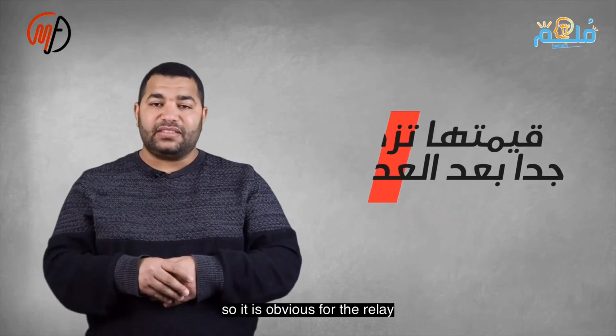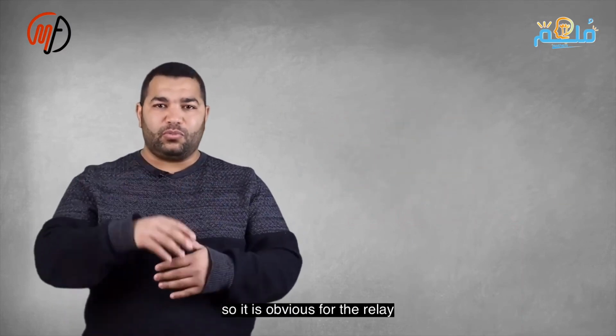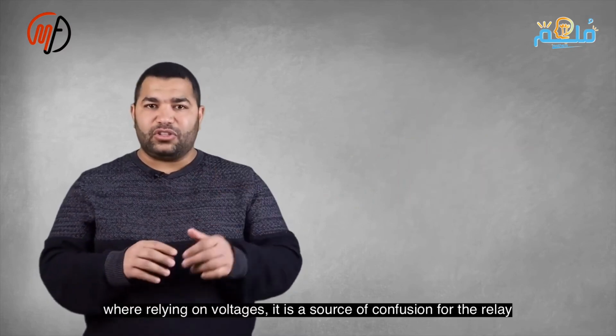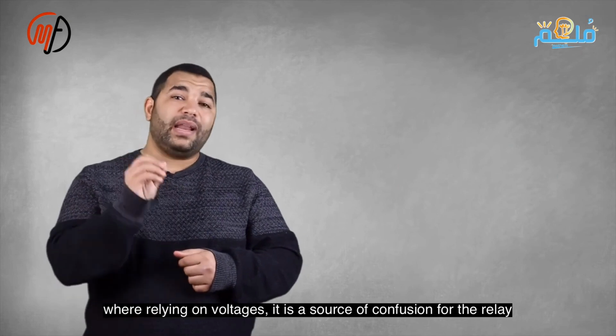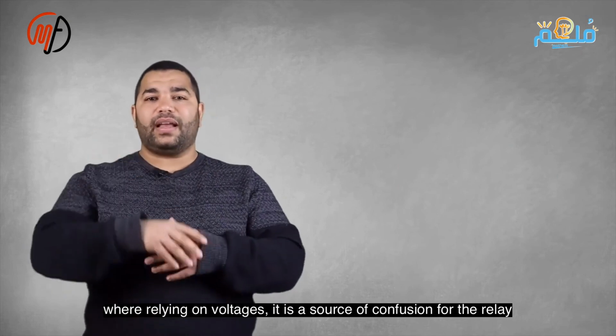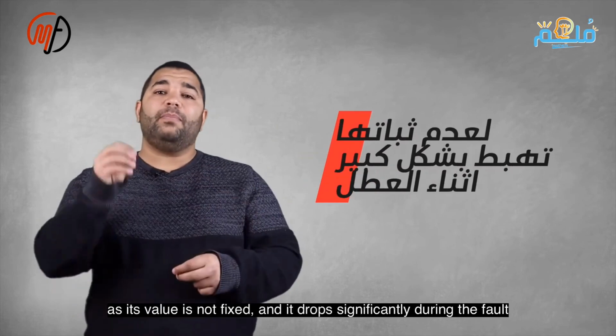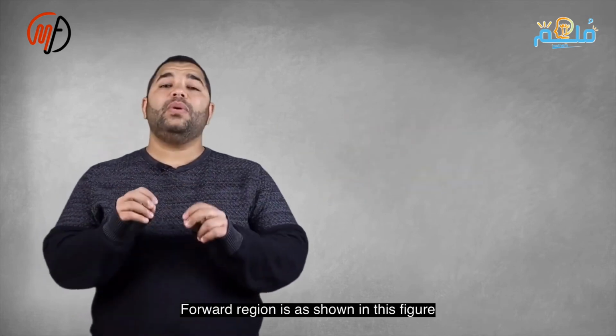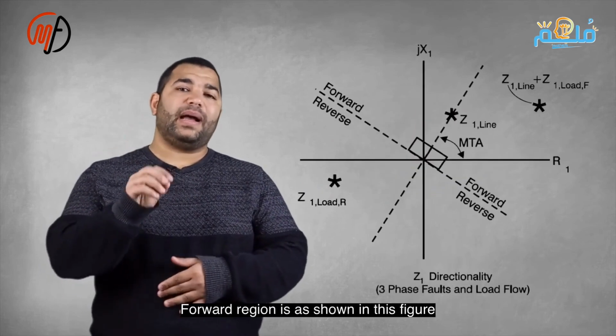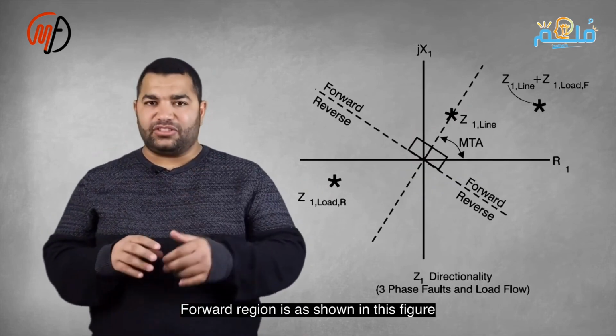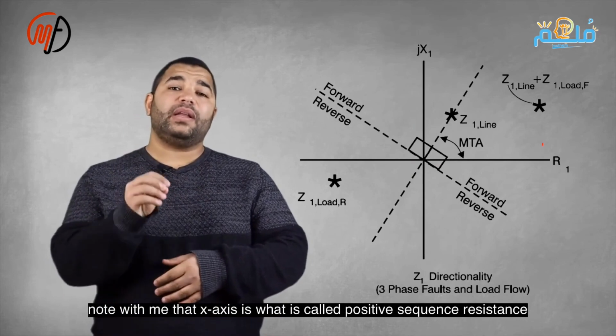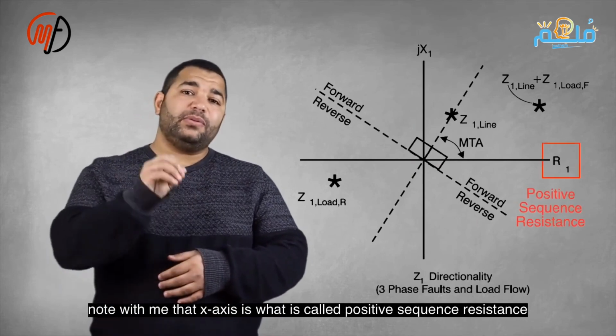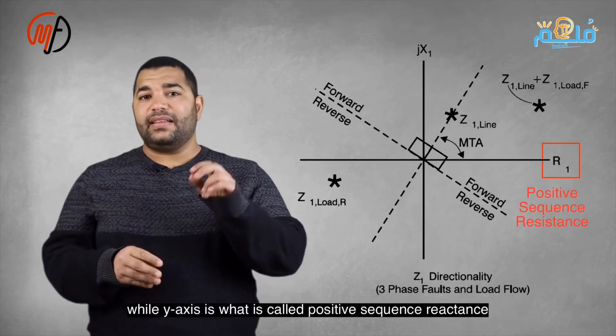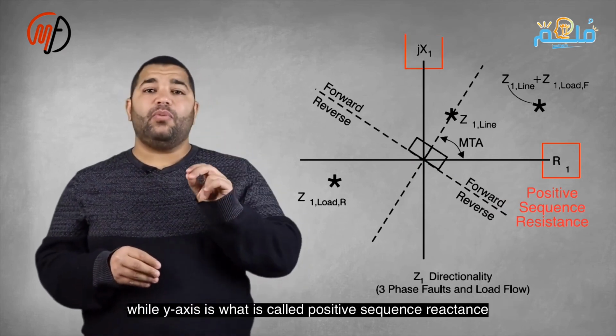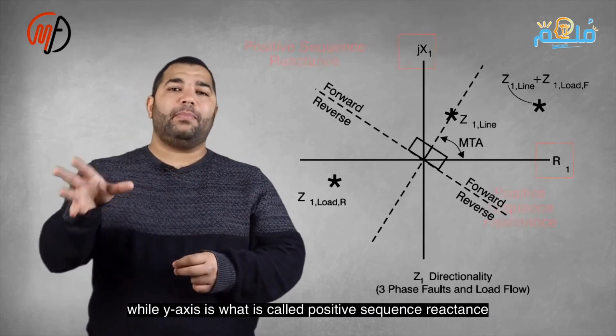The area is as shown in this diagram. The x-axis is the sequence resistance, while the y-axis is what we call the positive sequence reactance. The forward direction will be towards the positive sequence impedance of the line, which is called Z1 line. Here we use the maximum torque angle as before, so the maximum torque angle rotates counterclockwise with respect to the R-axis as the reference.